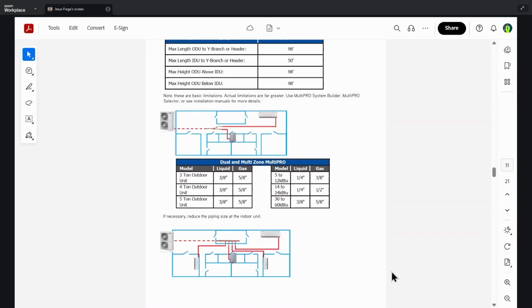So moving on here, dual and multi-zone MultiPRO. As we stated earlier, these are the line set connections for the outdoor units. We know they're all 3/8, 5/8, so no confusion there. This changes from the 410A models as 5 through 12K stay 1/4 inch to 3/8 line set connections for the indoor units, where before 3/8 would take us up to or down to 9,000 BTUs, and it would change at 12,000 BTUs to 1/2 inch.